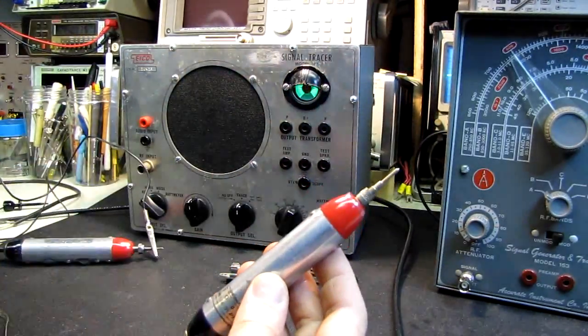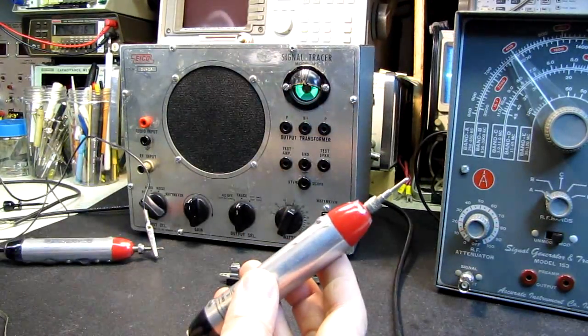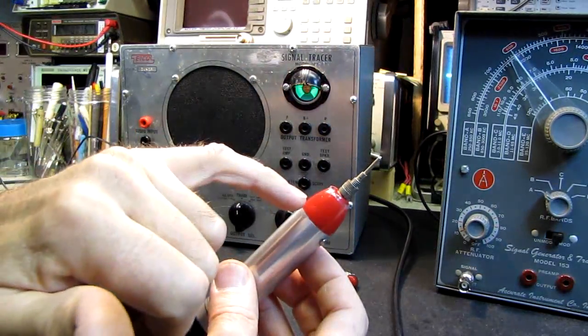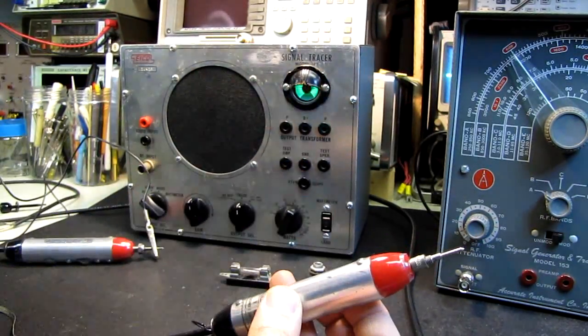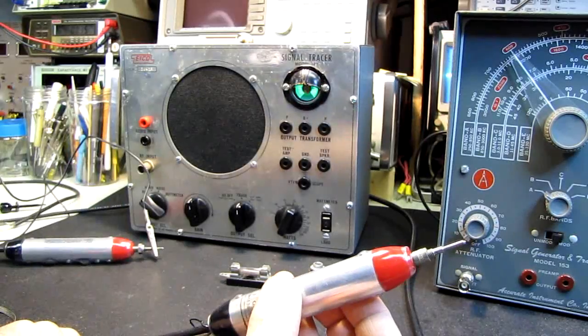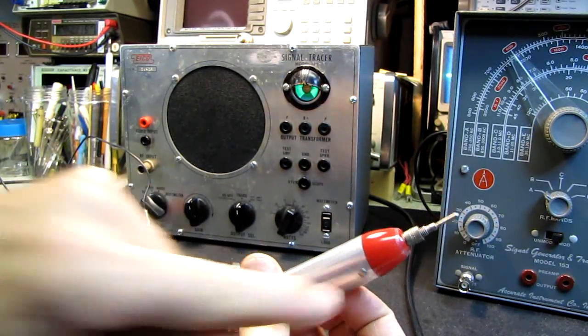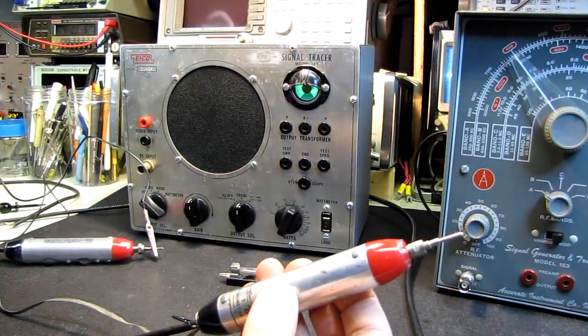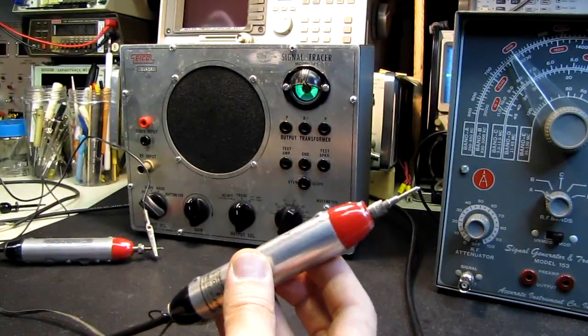People never bother backing them up and feeling the original thread when they run them in. They just screw them in. They cut new threads. Three or four insertions, there is no more aluminum left to bite. The wall thickness of these plastic parts is fairly substantial - about a quarter of an inch. Run a 2-56 tap down through, use a standard machine screw, they'll tighten right up again. If those ever wear out, you can go to a 4-40 thread, re-tap them. The plastic is fairly robust.